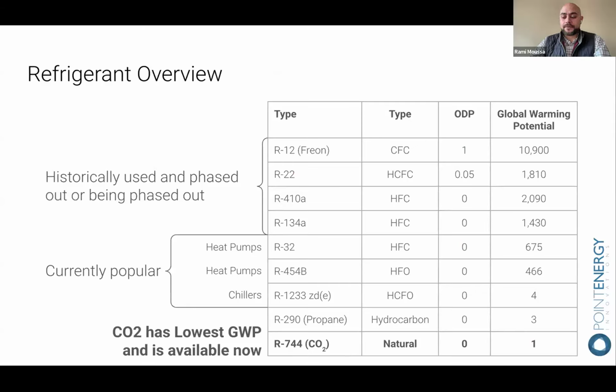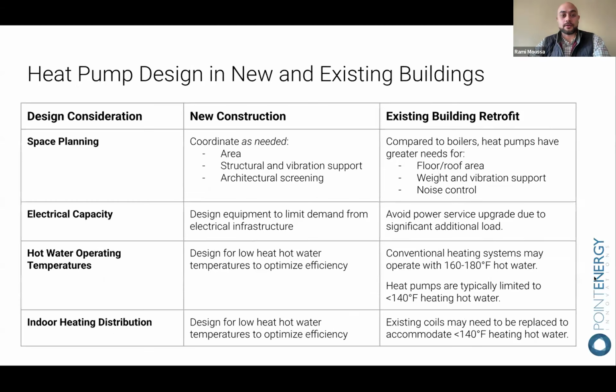Now, as I mentioned, that policy driven by the EPA is really pushing the global warming potential of refrigerants lower and lower. From the top of this chart, we're seeing those phased out in lieu of this middle section of the chart here with R32 and 454B. We see this global warming potential dropping further and further. You can't go much lower than CO₂. Carbon dioxide is basically the reference point for all other GWPs. And when we think about future proofing or getting ahead of legislation, that is about as good as it will get. And seeing the historic trend, we do continue to see more and more stringent requirements on refrigerants.